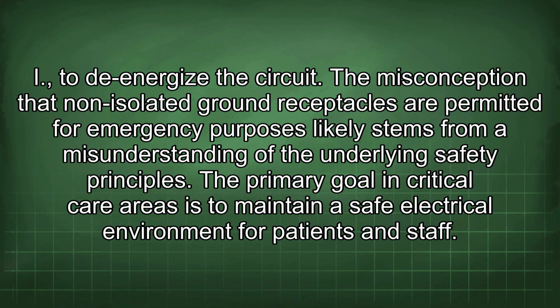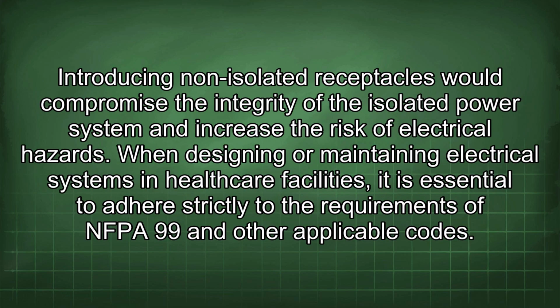The misconception that non-isolated ground receptacles are permitted for emergency purposes likely stems from a misunderstanding of the underlying safety principles. The primary goal in critical care areas is to maintain a safe electrical environment for patients and staff. Introducing non-isolated receptacles would compromise the integrity of the isolated power system and increase the risk of electrical hazards. When designing or maintaining electrical systems in healthcare facilities, it is essential to adhere strictly to the requirements of NFPA 99 and other applicable codes.